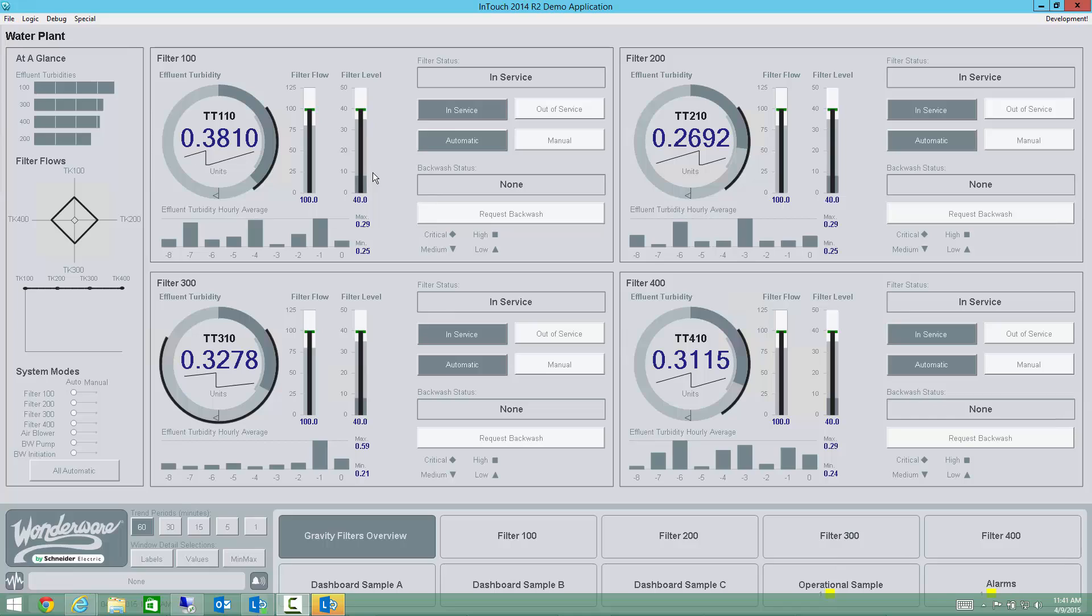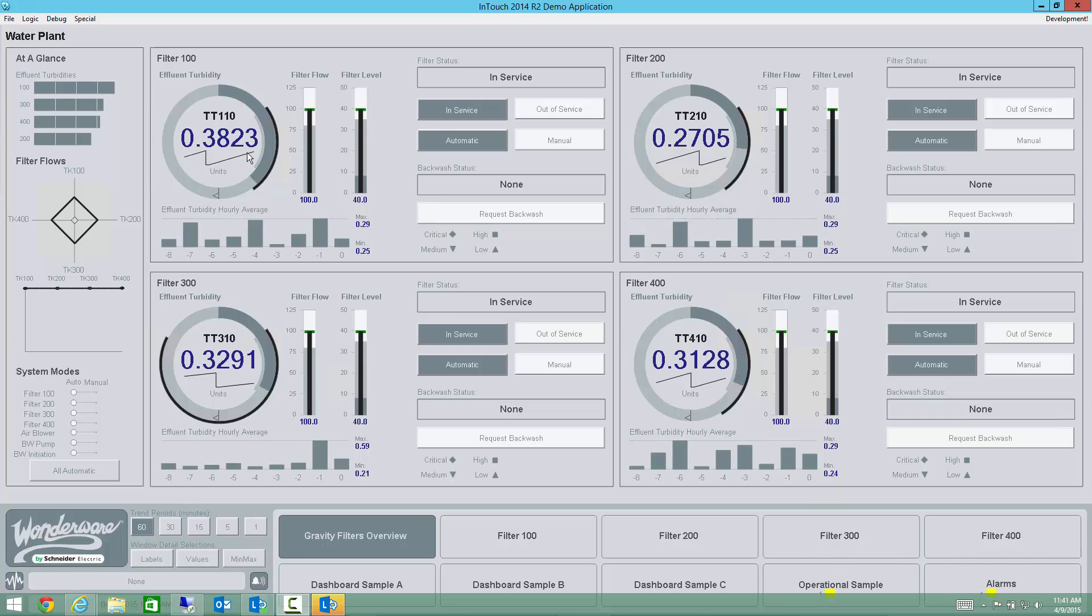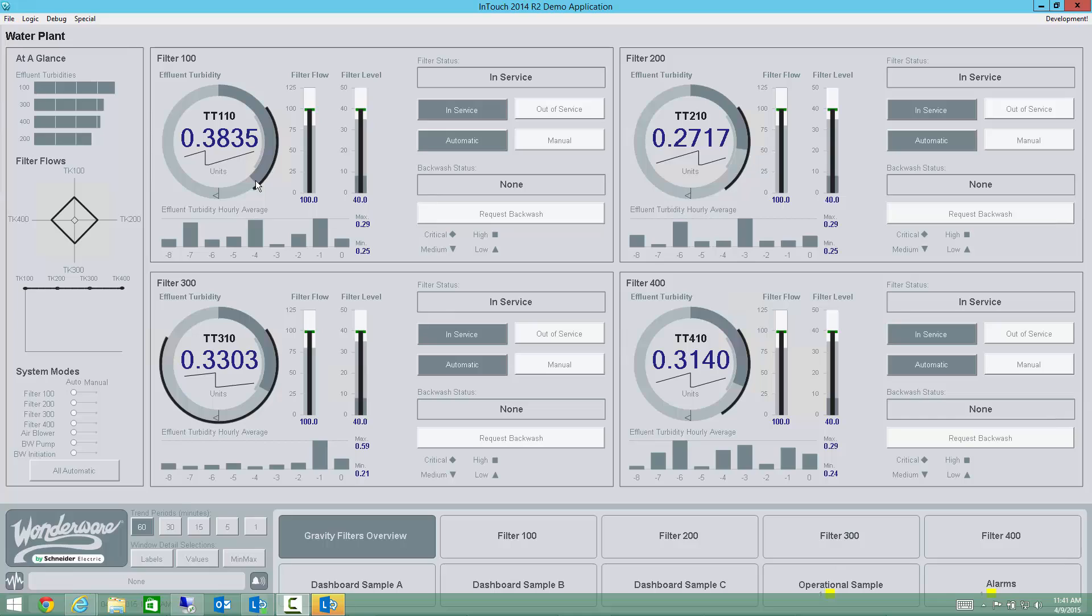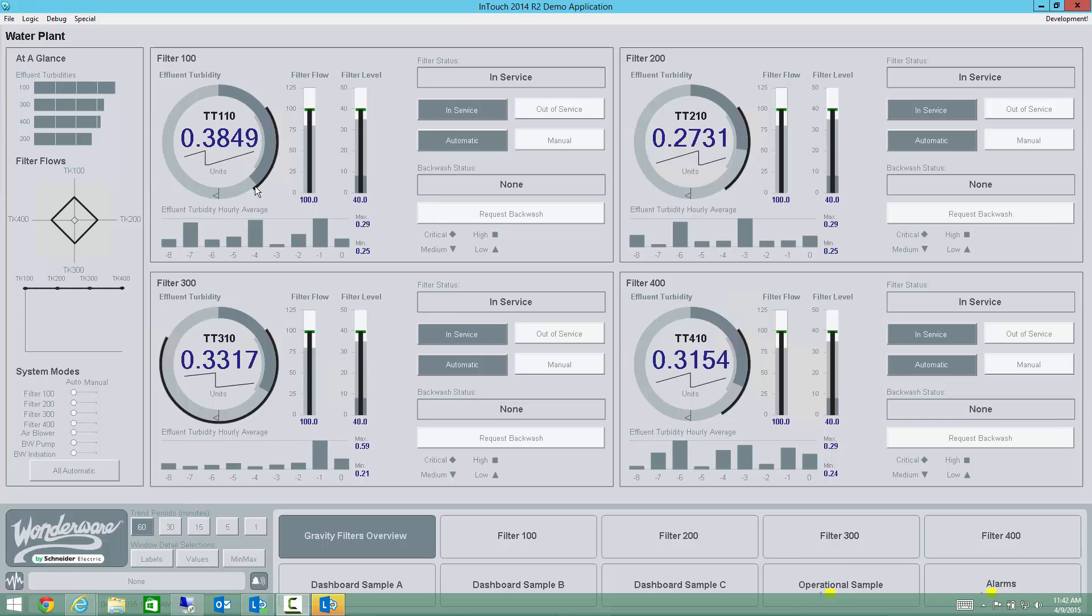But if we center in on the effluent turbidity here for a moment, it's showing me a lot of information about the effluent turbidity. It's showing me its current value numerically. It's showing me a trend of that value. And that trend is currently over the last 60 minutes or one hour. I'm able to see the current value again in a visual representation here. So this radius of this pie segment, if you will, here that's showing me that. I'm seeing a highlight here, which is showing me the optimal range. So I can see that I'm currently outside of my optimal range. And I might want to take a deeper look at that. And I can also see a darker line on the outside, which says where I've been over the current time of focus. So my current time of focus is the time period I'm setting down here in the bar area.